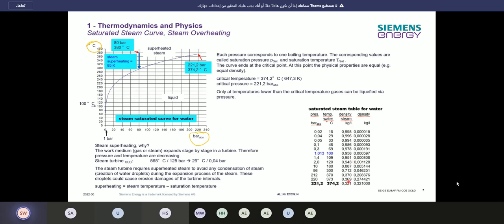And this is, of course, the case when you go onto the power plant and you see the pipes and the HP piping, because you have the higher pressure, you have then the higher density of steam. So you will have the smaller diameter for the HP piping.